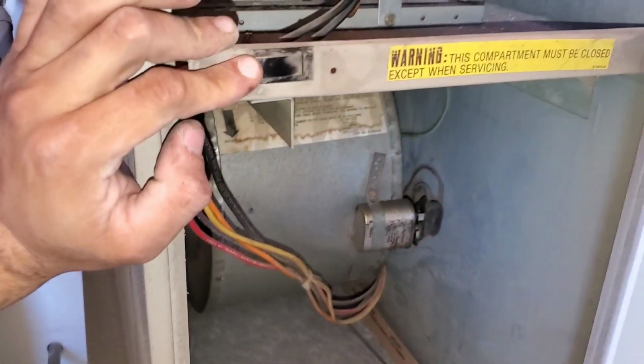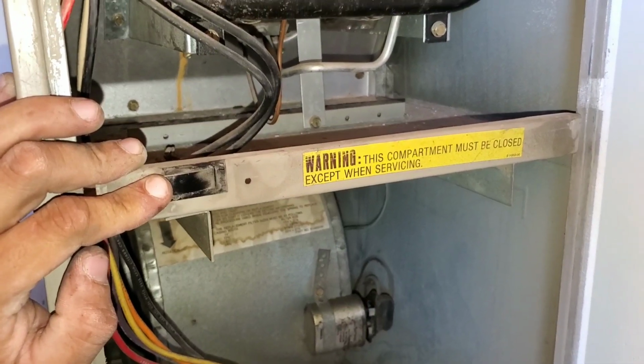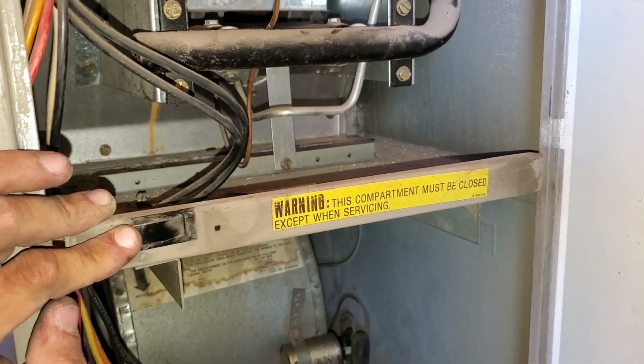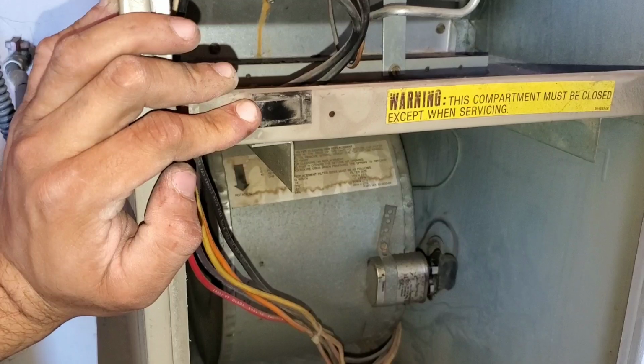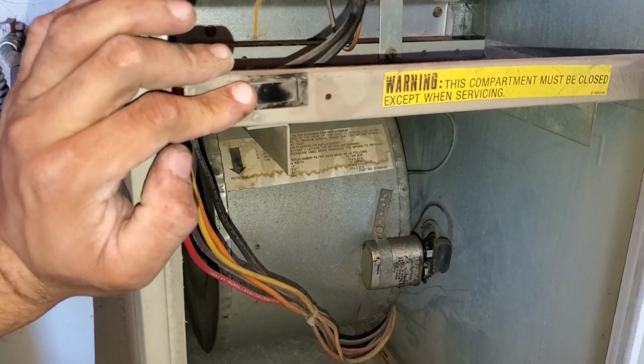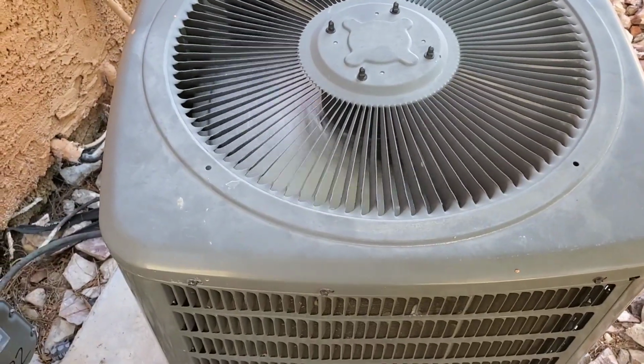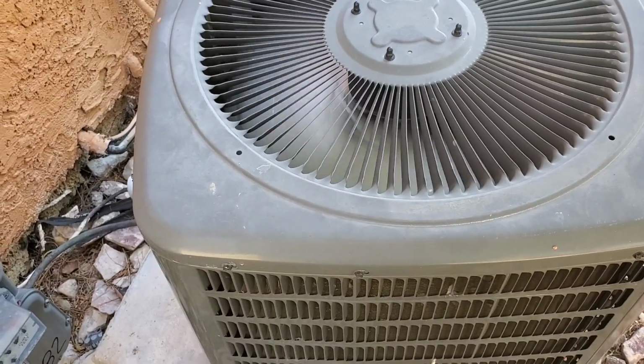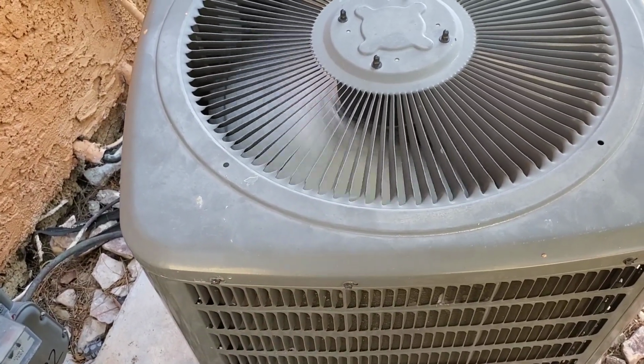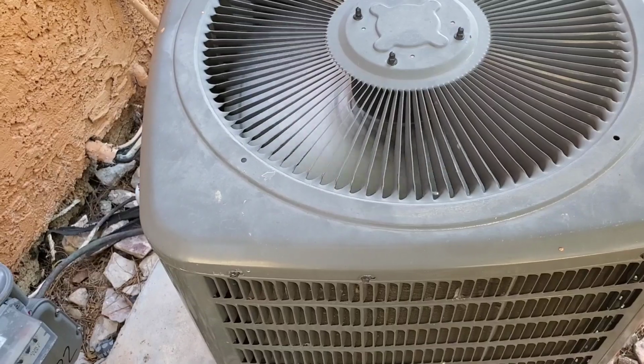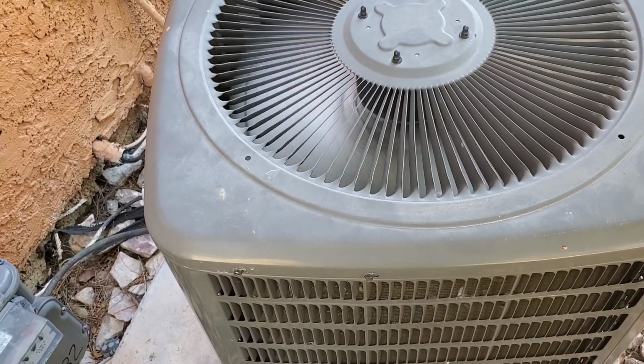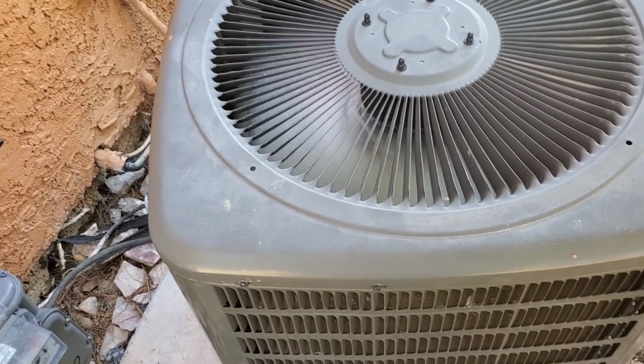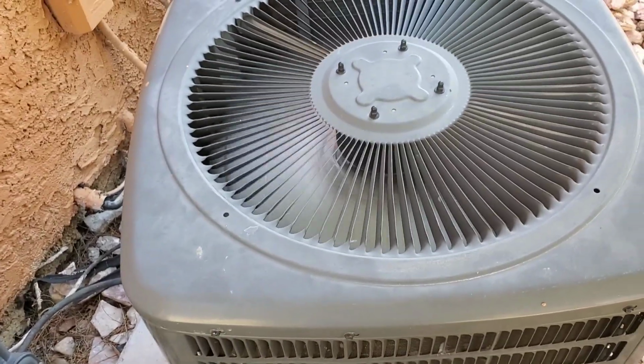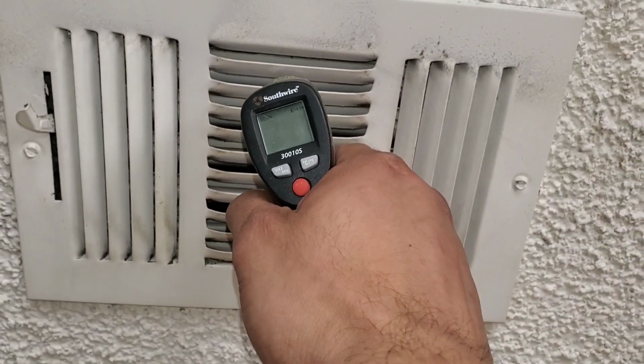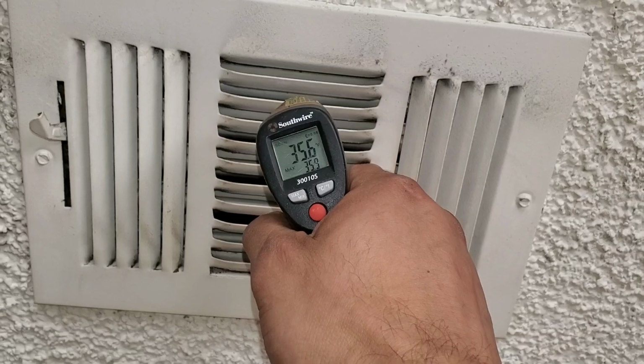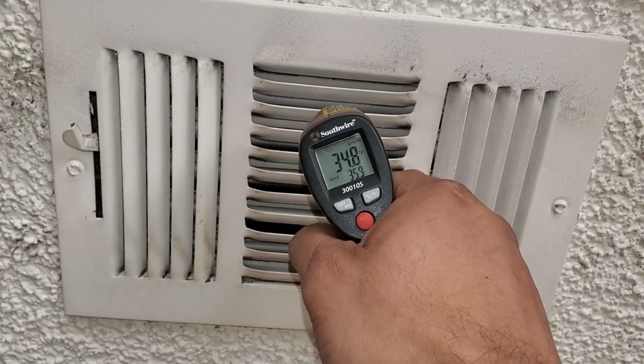So we know at this point, step number one, the thermostat is working. Step number two, the blower motor is working at the return. So now we're going to step number three. So here we are, step number three. We're at the condensing unit. You can see the condenser fan motor is running. I hear the compressor running. So right now we just know this is how the system would operate if everything was running and functioning properly. And now we're just going to take the temperature. And you can see that our system is operating properly.